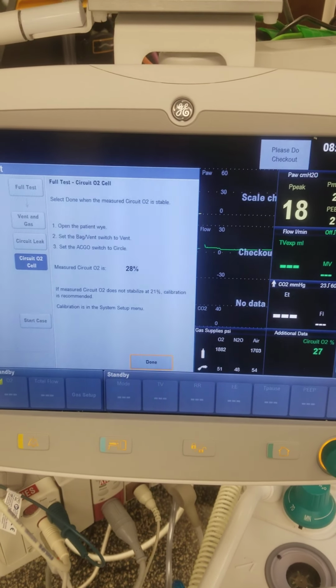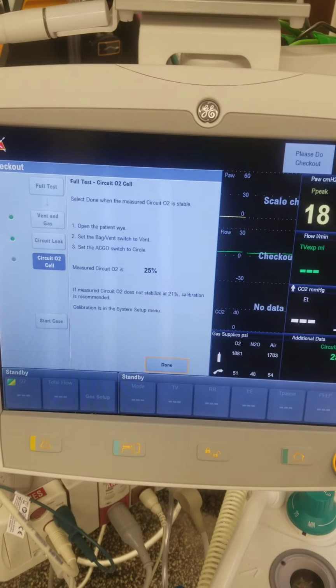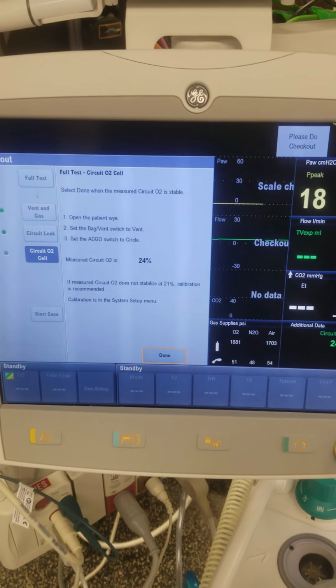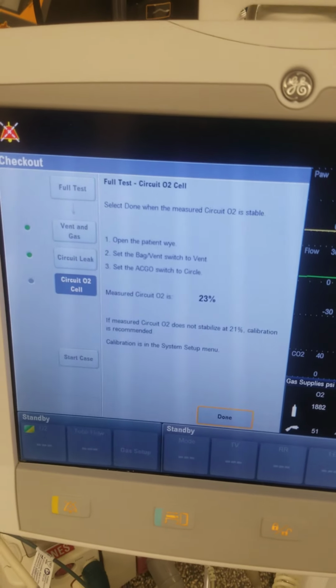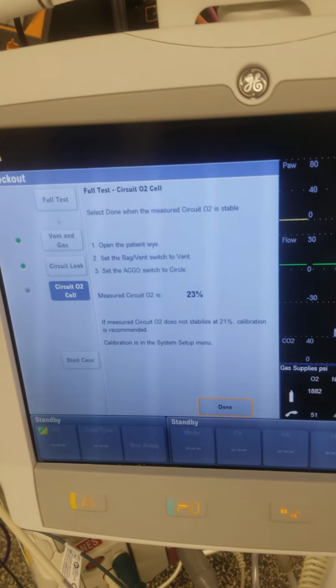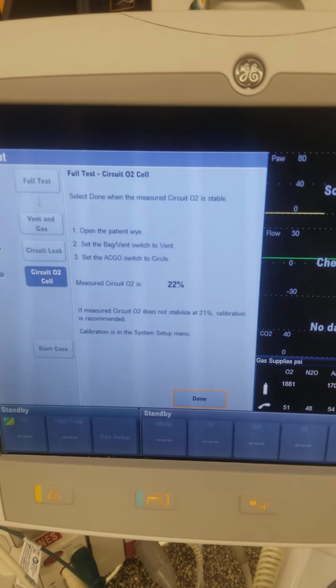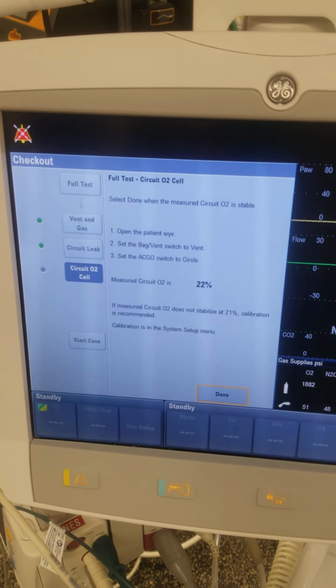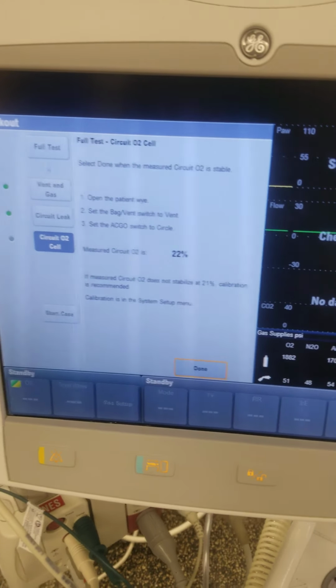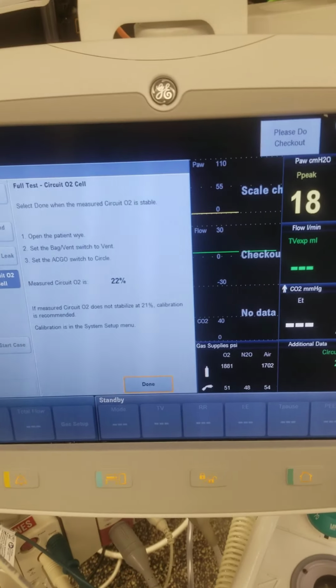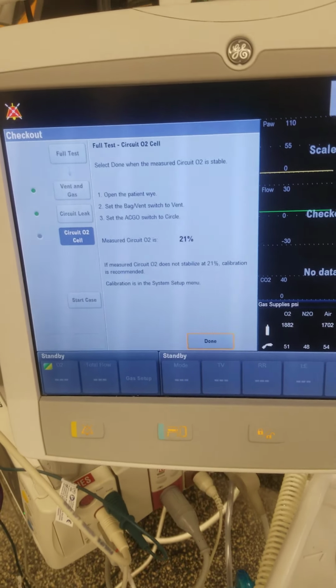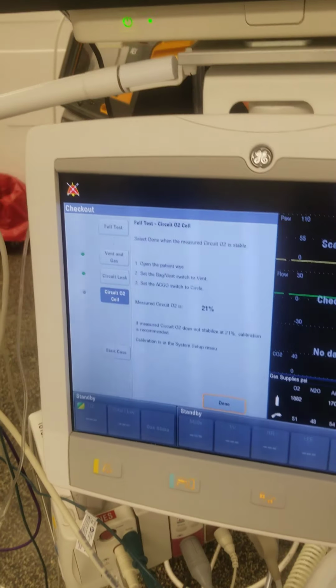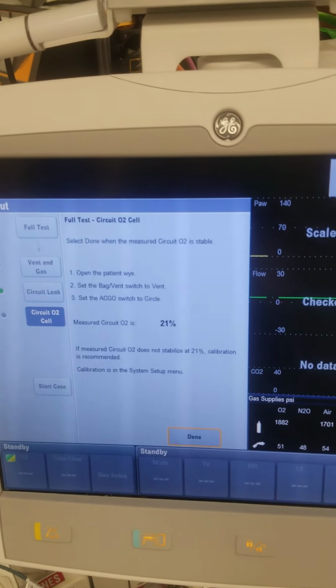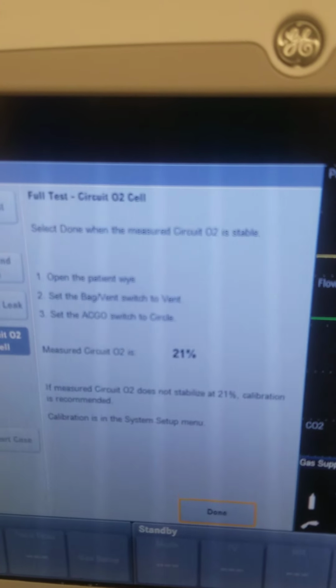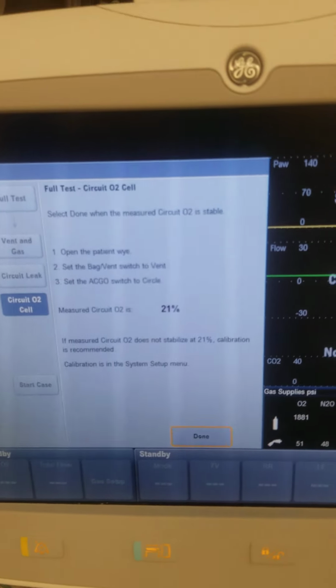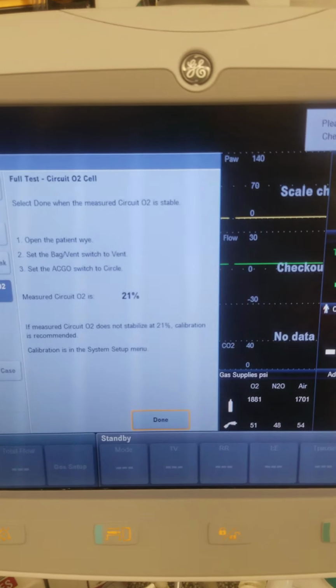So what it wants you to do is see if the FiO2 goes to 21% and stays there. Sometimes the O2 sensor needs to be calibrated, and it's going to read like 17% when we know that right now in the room that we're breathing, it's 21%. So if you're reading a number that's really far off from what the room is, which is 21% oxygen, which it is in the whole world, you need to recalibrate your O2 sensor, which I think I'll show you right now because most people don't know how to do this. So good to know. If, instead of staying stable at 21%, it says anything other than 21%, it's time to do the O2 sensor calibration.